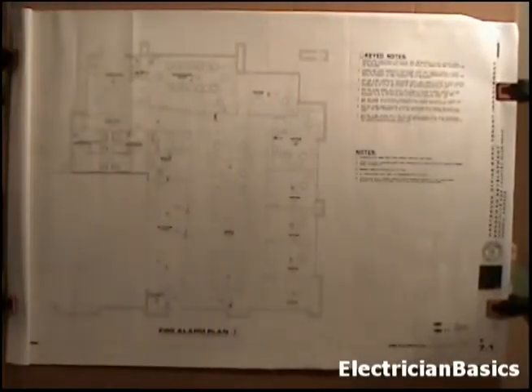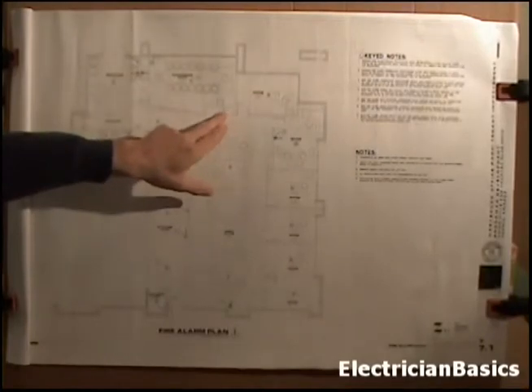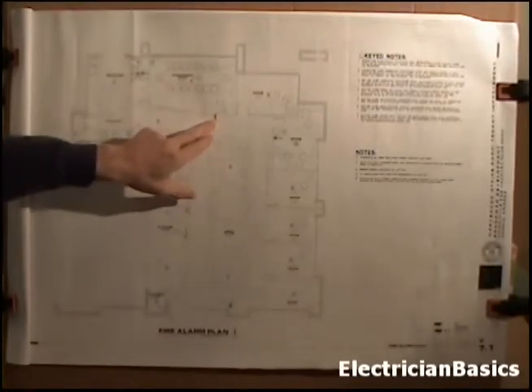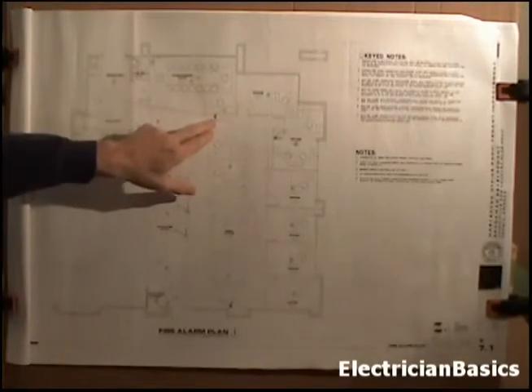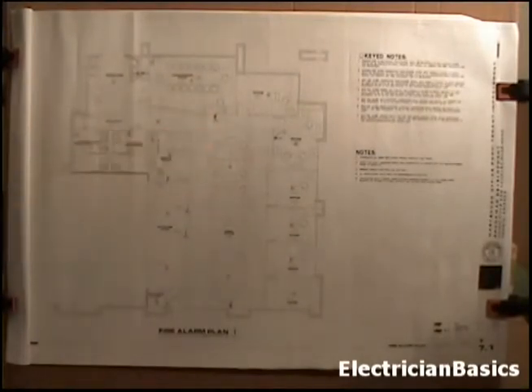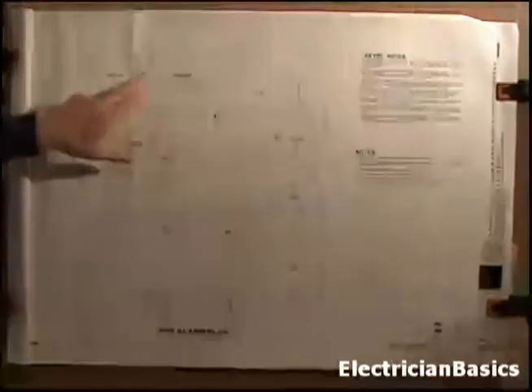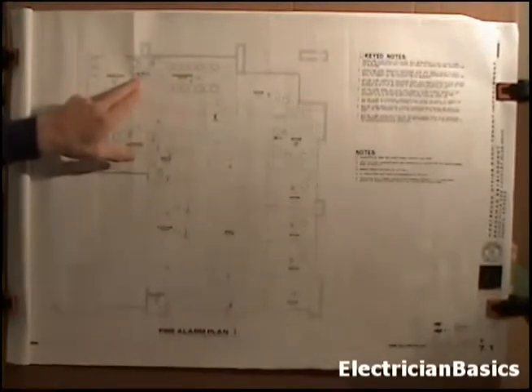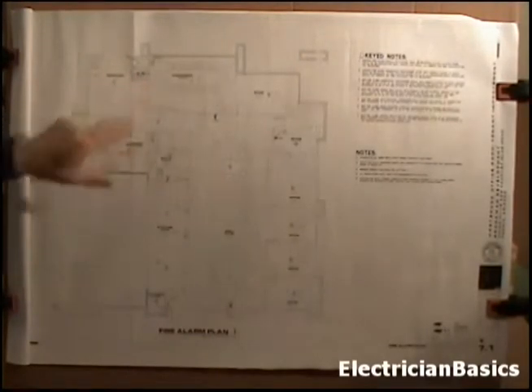So we're back on sheet E7.1. I'm going to point out now, here's a note 2 on a key note, and it's got a device. Look at this symbol. We have a square with an X and a circle and a little triangle. And that symbol, remember, we saw on sheet E0.1, but it says existing fire alarm combination horn strobe device with candela rating as noted. So that's a horn strobe. Note 3, it's the same device as well, and it said they should be mounted at 80 inches above finished floor.